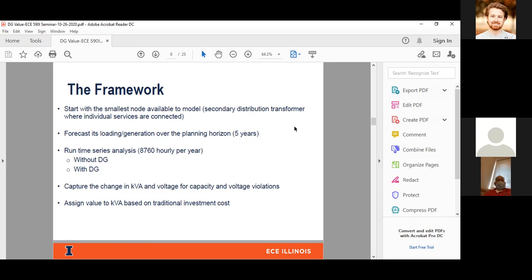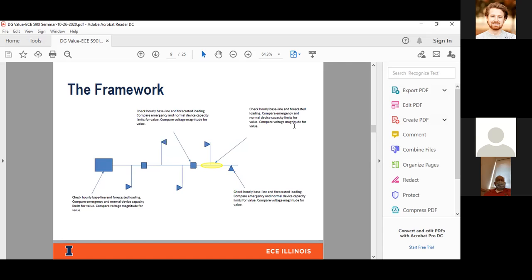So we captured the range of kVA and voltage change for different capacity and voltage violations, again, based on that planning criteria. And then we assign value to the kVA based on traditional investment cost. This is what, on a high level, a distribution feeder might look like. On the left-hand side, that's where the feeder head starts at the substation level. And then going downstream to the right, you will see the different components that are evaluated in the planning process.